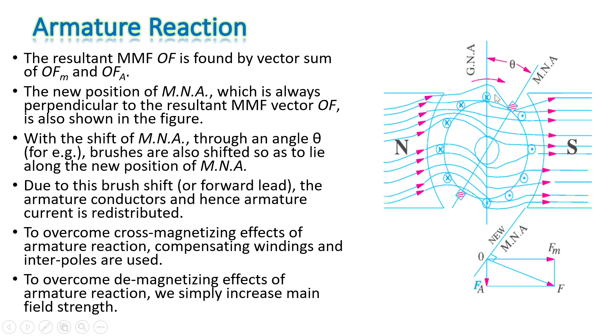The brushes that were placed on the original axis now need to be placed on the new axis. Due to this brush shift or forward lead, the armature conductors and hence the armature current are also redistributed — one conductor now has current going inward and another has current coming outward. So the main effects of armature reaction are: it cross-magnetizes, changing the direction of the main field, and it demagnetizes, weakening the main field. To overcome cross-magnetizing effects, compensation windings and interpoles are used; to overcome demagnetizing effects, the main field strength is simply increased.